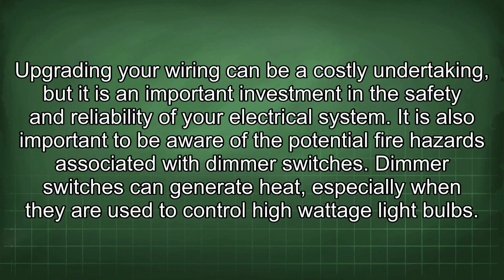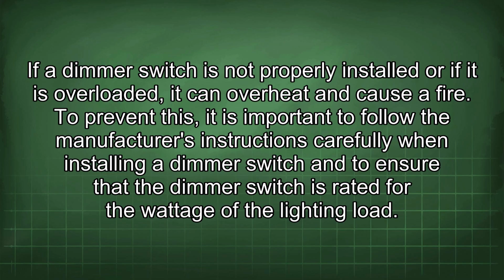your electrical system. It is also important to be aware of the potential fire hazards associated with dimmer switches. Dimmer switches can generate heat, especially when they are used to control high wattage light bulbs. If a dimmer switch is not properly installed or if it is overloaded, it can overheat and cause a fire. To prevent this, it is important to follow the manufacturer's instructions carefully when installing a dimmer switch and to ensure that the dimmer switch is rated for the wattage of the lighting load.